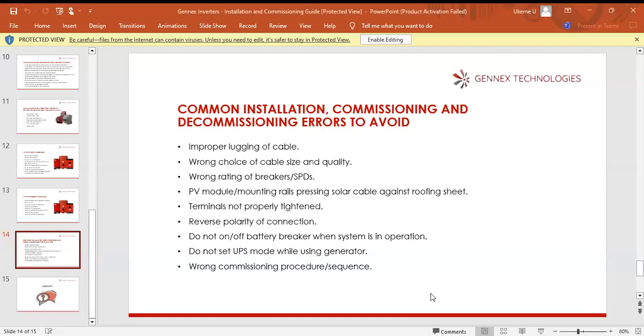Yeah, I was talking about the wrong choice of cable size and quality. If the cable is the correct size but of wrong quality, there will be loss of power. The cable will be heating, which can lead to fire. It can damage the terminal of the inverter and circuit breakers, because there will be heating at the terminals. So a lot of things. The best thing is to get things done right and use the right components.